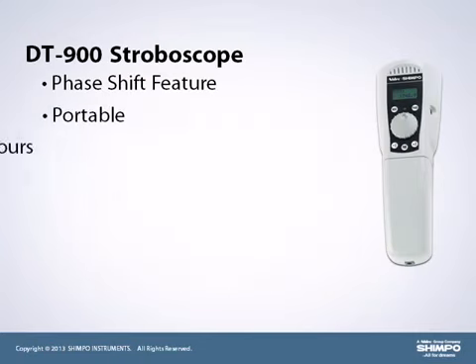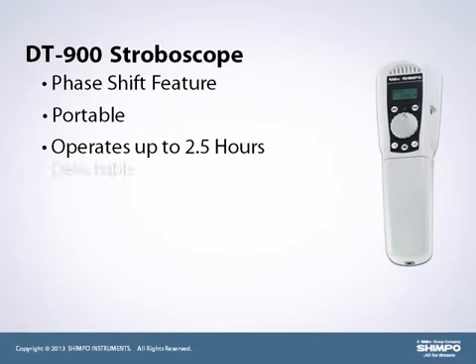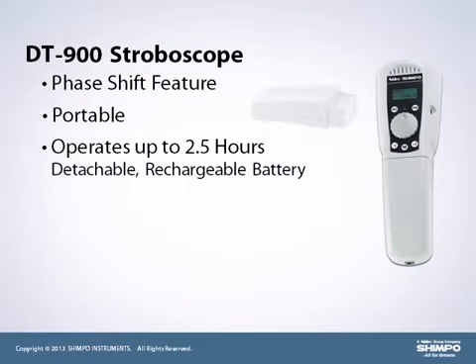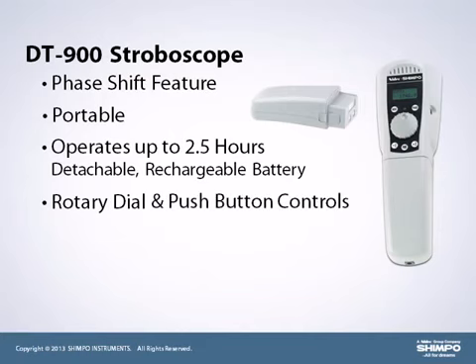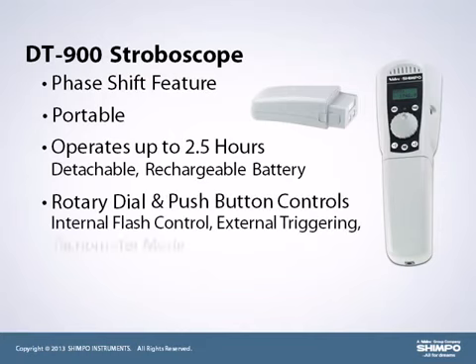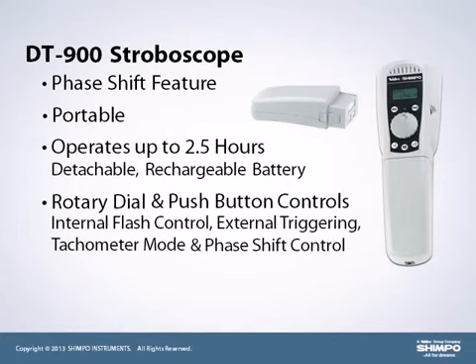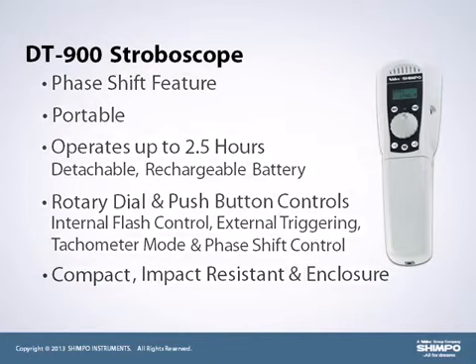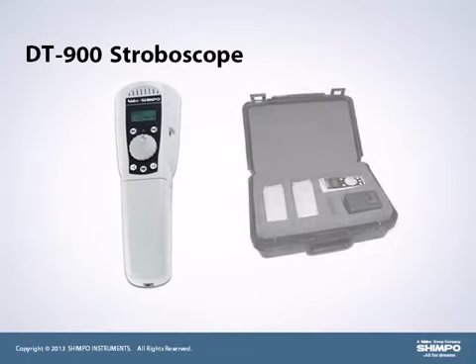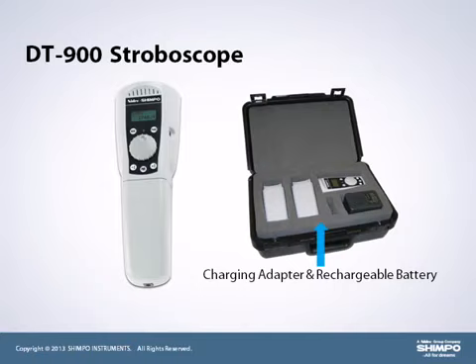The unit is completely portable and operates up to 2.5 hours on its detachable, rechargeable battery. The battery is quickly detached and recharged while another battery is snapped into place. Quality and maintenance professionals will appreciate the rotary dial and push button controls for internal flash rate adjustment, external triggering, tachometer mode, and phase shift control. The push buttons rapidly increase or decrease by a factor of 2 the flashes per minute and change by degrees the flash phase. The DT-900 has a compact, impact-resistant, and rugged enclosure that withstands demanding usage. Units come standard with a charging adapter as well as one rechargeable battery.